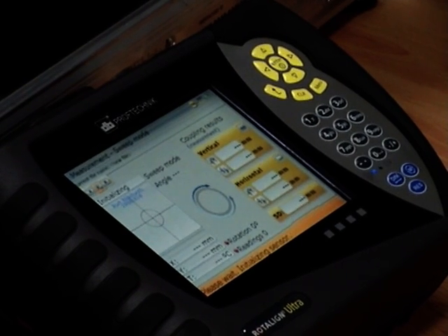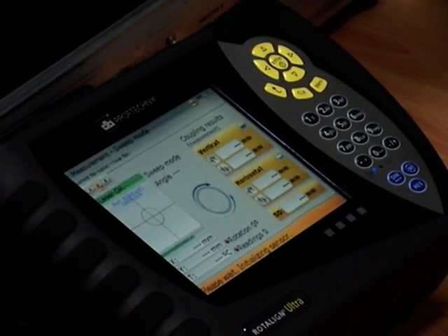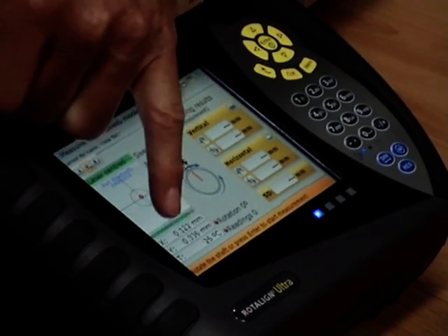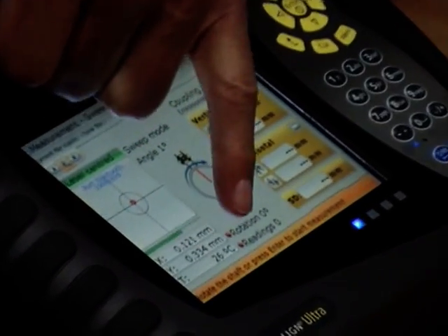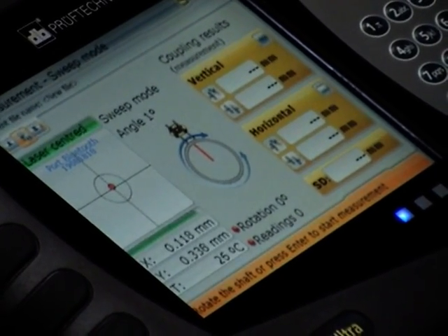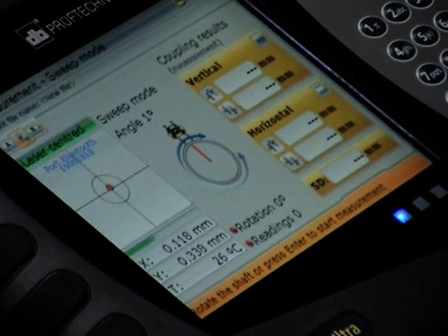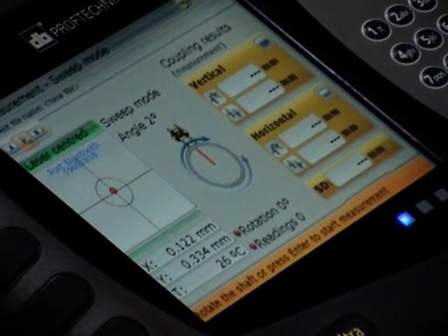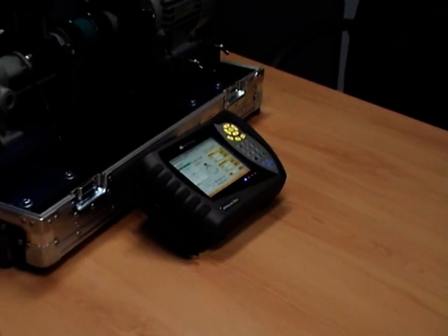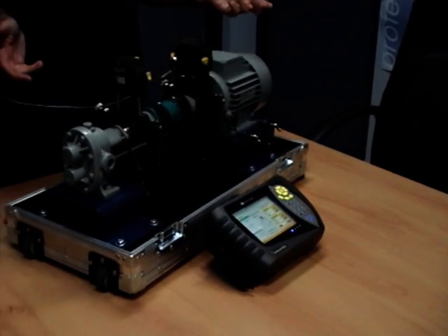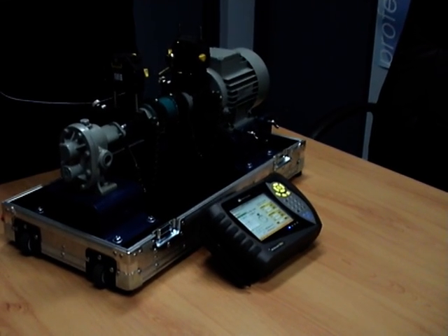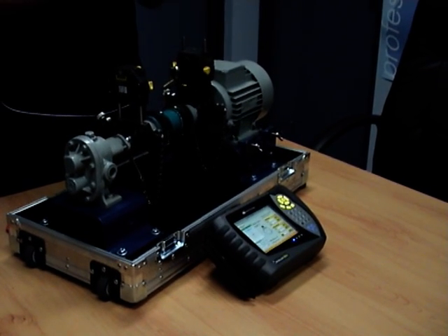Just again initializing the Bluetooth. Okay, so we're ready to go. The message at the bottom there says rotate the shaft to start or press the enter. Basically the inclinometer is live on this. We said we've got the two detector planes, we also have an electronic inclinometer and that knows what the angle is to a tenth of a degree. With this particular tool we can start anywhere and we can stop anywhere. It'll just when it starts getting some new data from the inclinometer and where we're hitting on the detector planes, it starts collecting a bunch of measurements.